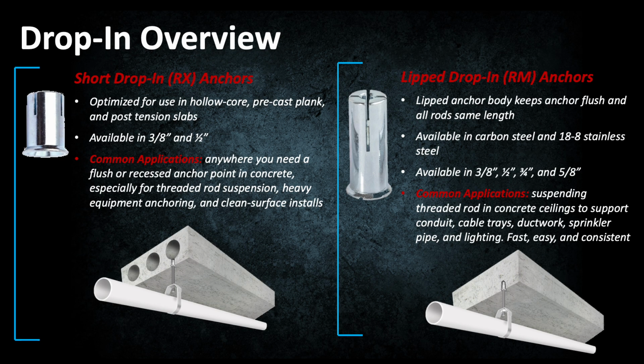Drop-in anchors give you a flush, threaded attachment point in concrete, which is ideal for suspending threaded rod. Short drop-ins, or RX style, are optimized for hollow core plank, precast, and post-tension slabs where embedment depth is limited. Lipped drop-ins, the RM style, keep the anchor body flush with the surface so all the rods end up at a consistent height. These are available in carbon steel and stainless steel and are commonly used for supporting conduit, cable tray, ductwork, sprinkler pipe, and lighting from concrete ceilings.